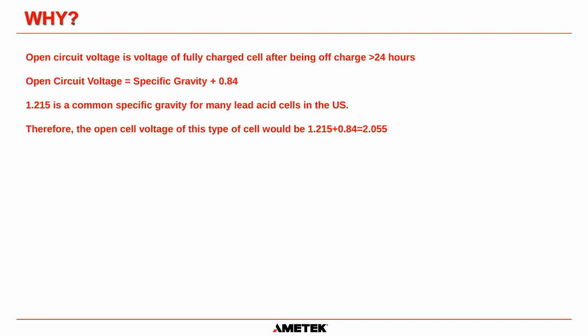On a side note, the open circuit voltage is the voltage of a fully charged lead acid cell after being off charge for a period greater than 24 hours. So basically, if you have a cell that has been disconnected from the charger and left for 24 hours, that cell is still fully charged, but we can actually get some information about the state of charge of that cell. And the equation is that the open circuit voltage should be the specific gravity number plus a value of 0.84. That's just an industry standard.